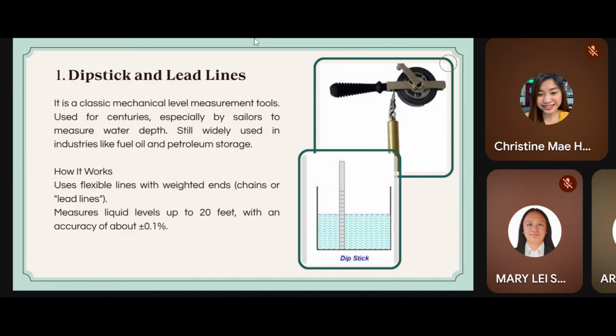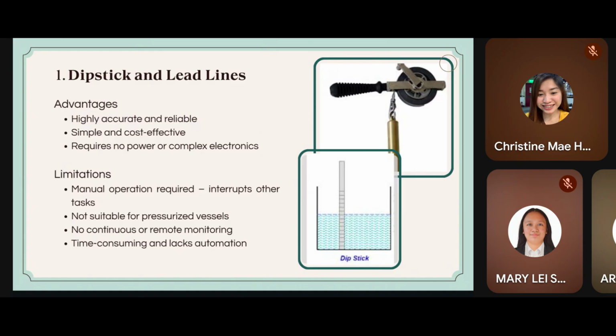Okay, the first one of these measuring instruments is, well, dipstick and lead lines. It is a classic mechanical level measurement tool which has been used for centuries, especially by sailors to measure water depth. Still widely used in industries like fuel oil and petroleum storages. How it works is it uses flexible lines with weighted ends, which are chains or lead lines, and measures liquid levels up to 20 feet with an accuracy of about 0.1%. It has many advantages, actually just three: it's highly accurate and easy to use, simple and cost effective, and requires no power or complex electronics. But it has its limits and its uses.